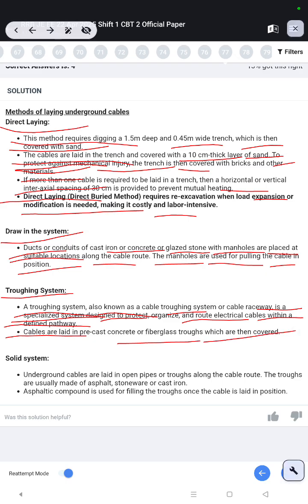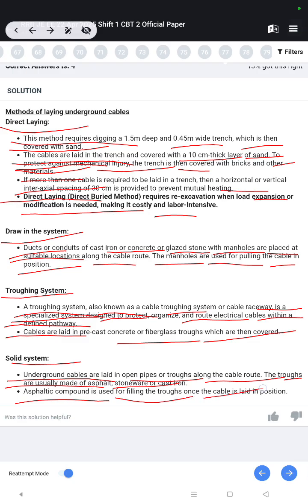Solid system. Underground cables are laid in open pipes or troughs along the cable route. The troughs are usually made of asphalt, stoneware, or cast iron. Asphaltic compound is used for filling the trough once the cable is laid in position.